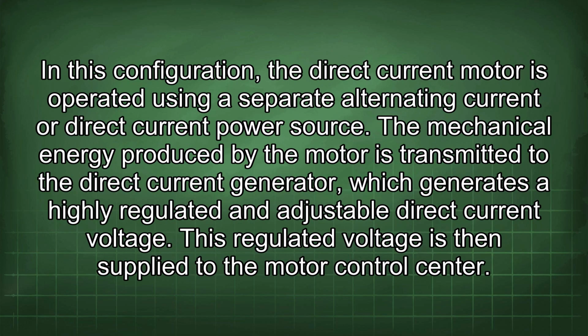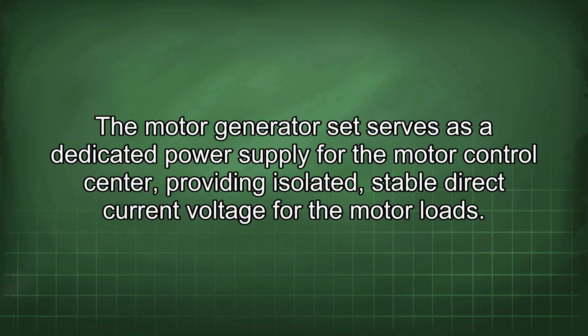In this configuration, the direct current motor is operated using a separate alternating current or direct current power source. The mechanical energy produced by the motor is transmitted to the direct current generator, which generates a highly regulated and adjustable direct current voltage. This regulated voltage is then supplied to the motor control center. The motor generator set serves as a dedicated power supply for the motor control center, providing isolated, stable direct current voltage for the motor loads.